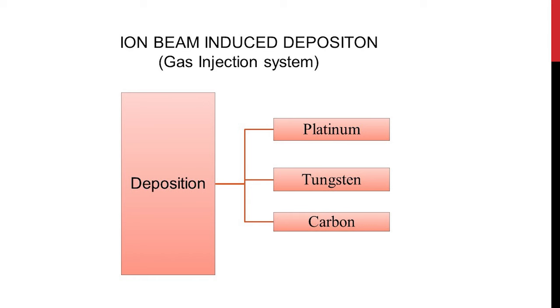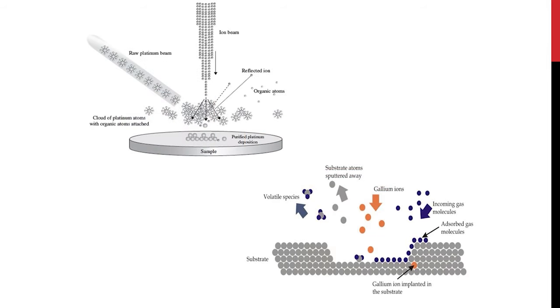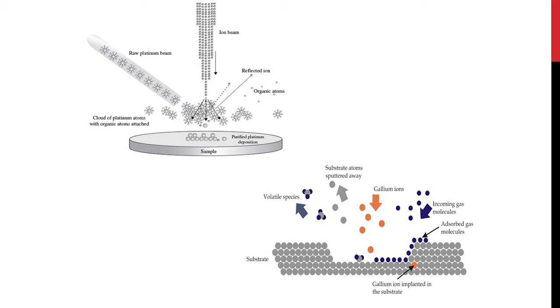The next module is ion beam induced deposition, which is termed as a gas injection system. We have three precursor gases — platinum, tungsten, and carbon — which are useful for in-situ deposition. The basic principle is that the gallium ion beam scans the sample surface. Taking platinum as an example: we have a platinum precursor with a single platinum atom surrounded by many organic atoms. When this interacts with the ion beam at 30 kV energy, the platinum atom gets deposited on the sample surface and all the volatile compounds leave. This way, we deposit layer by layer of platinum on the sample surface.